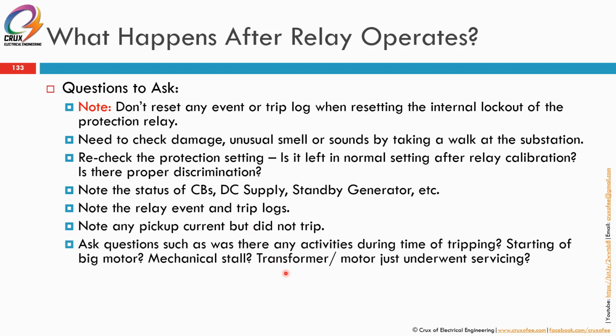So you will also have to ask questions such as, was there any activity during the time of tripping? Maybe someone was working at the substation, or working on the overhead line, or near the ABC aerial bundle cable. And then maybe at the time of the trip, a big motor was starting, or a new motor was just commissioned but we have not yet adjusted the upstream incomer setting. So maybe that caused the trip. Or maybe there was a mechanical stall, so the big motor stalled. Or was there any transformer or motor that just underwent servicing. So these are the typical conditions that may cause electrical issues like flashover, short circuit, things like that, that will trigger your protection.